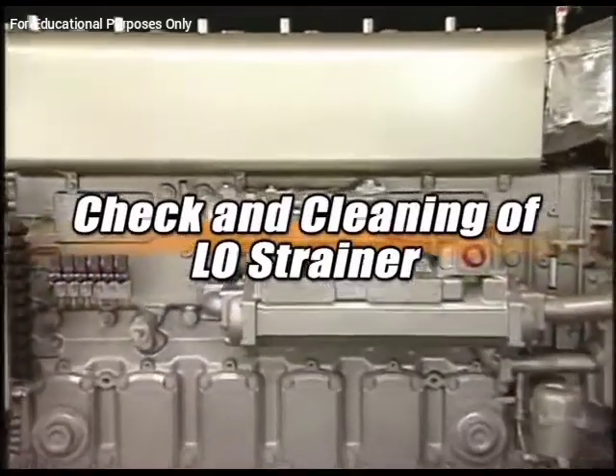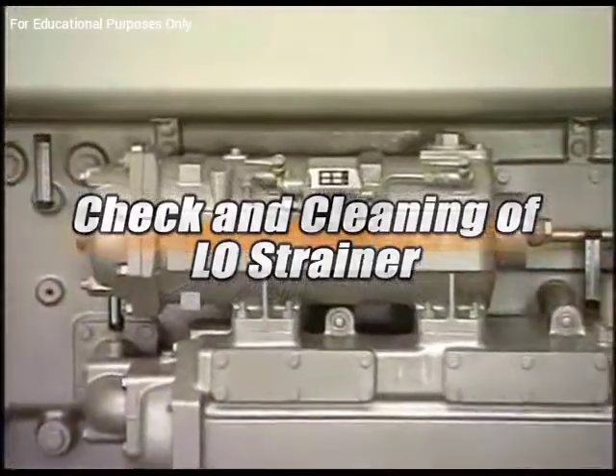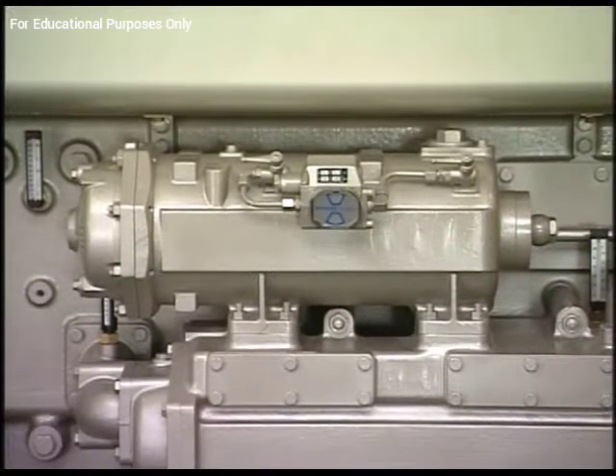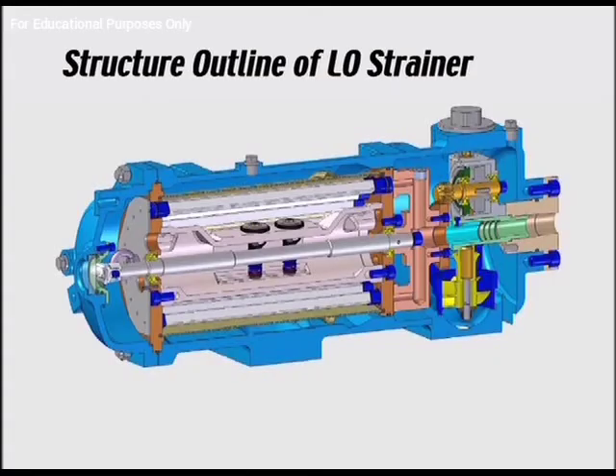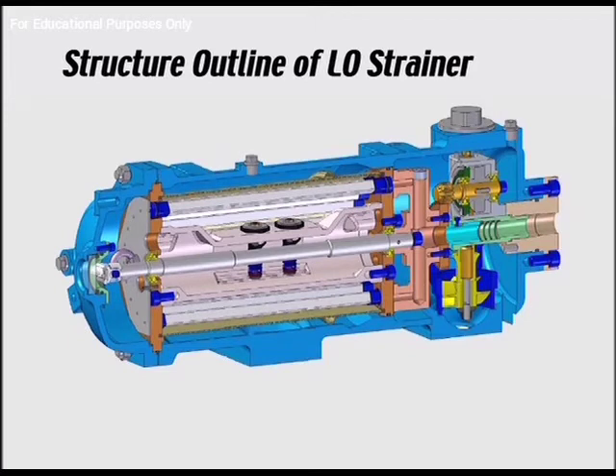The lube oil strainer fitted on this engine is the automatic backwashing filter. Lube oil is filtered by running from the inside to the outside of the strainer element. The cleaning nozzle rotates during operation by a turbine driven by lube oil pressure. At the tip of the nozzle, the flow of lube oil is reversed, dirt is discharged, and filtration and cleaning are constantly repeated.